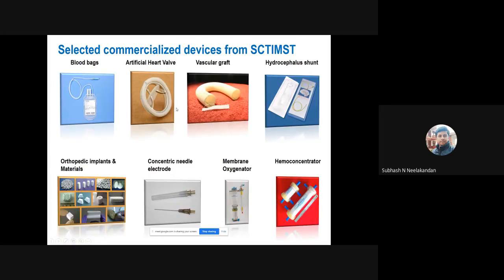Again, the risk of the heart valve device is much bigger when compared to a hemoconcentrator or a membrane oxygenator. So after taking into account the risk level and the functionality, we need to first plan what the device verification activities are, and based on the verification activities only, subsequent tests will be performed. So this concept of user requirement to design input to process to output in a medical device will hold true. But within these steps, the activities carried out will vary from device to device.